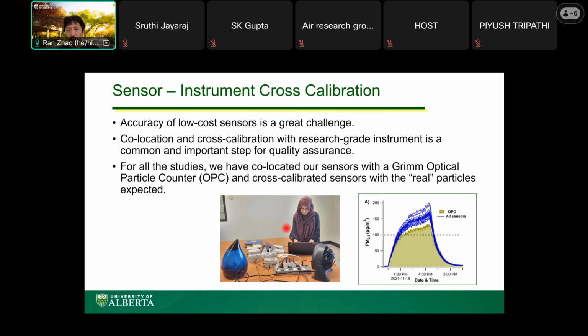And the diagram on the right-hand side is example data, a time series of PM2.5 over time for the intercomparison study. The blue lines here, many of them, are all the microsensors, the low-cost sensors that we studied, put in the room. And the yellow shaded area is the reading by the optical particle counter, the research-grade reference instrument. As you can see, the agreement is pretty reasonable up to 100 micrograms per cubic meter, but there is some deviation above that. So what we did is apply a sensor-specific calibration or correction factor to ensure that the accuracy of the sensor is reasonable.